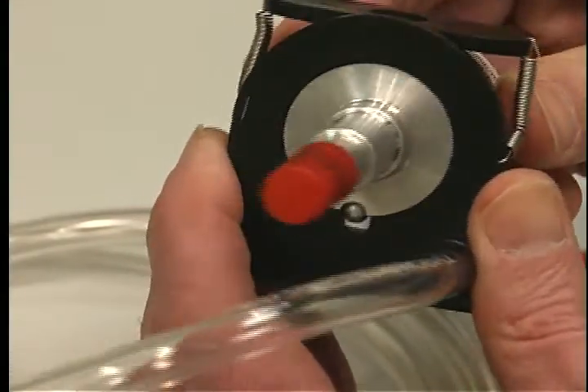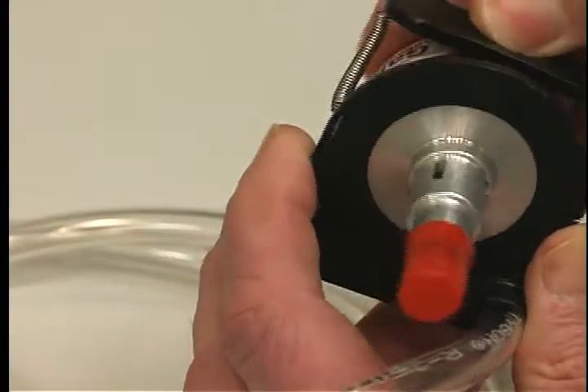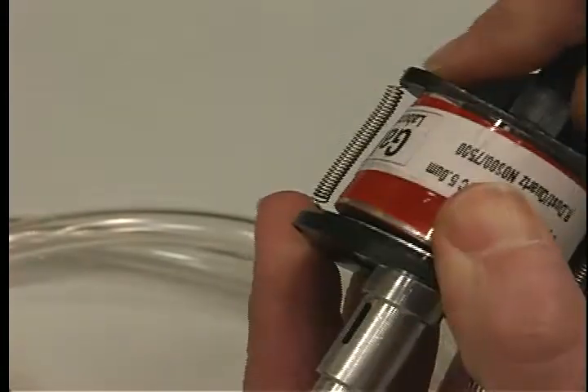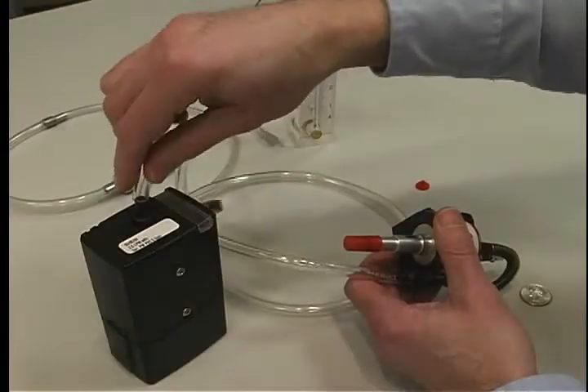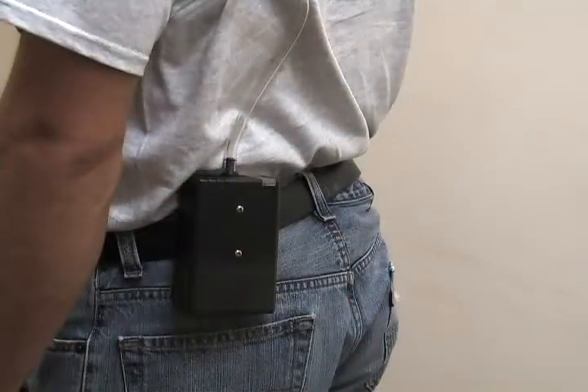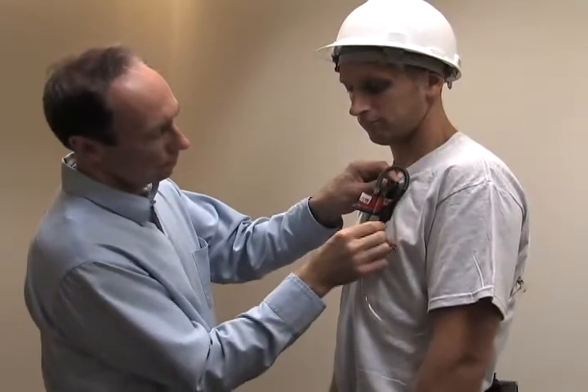The black O-ring will secure it in place. Place the attached filter cyclone in the cyclone holder, inserting the cyclone side pin into the notch in the cassette holder. Then attach the black tubing to the wagon wheel side of the cassette. Attach the Tygon tubing to the pump inlet. Attach the pump to the worker's belt or pocket, either in back or on the side.